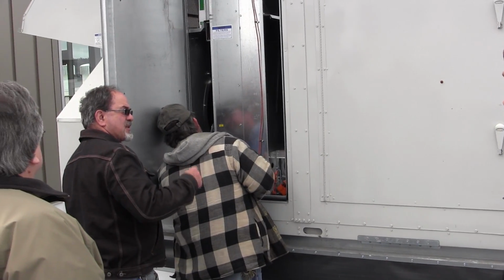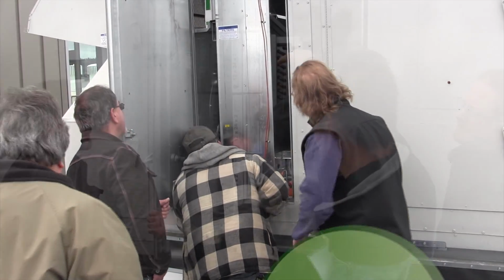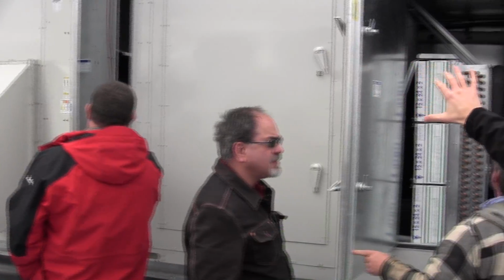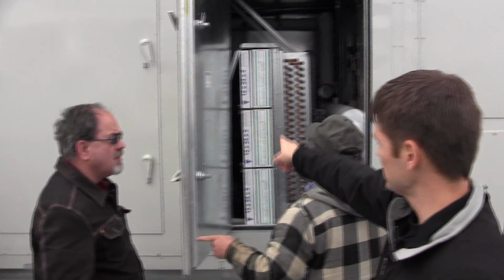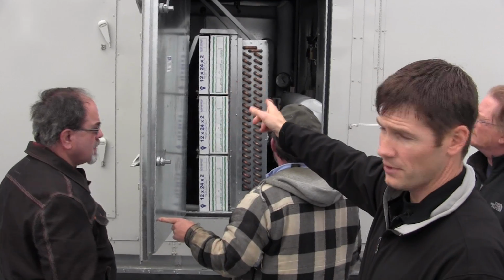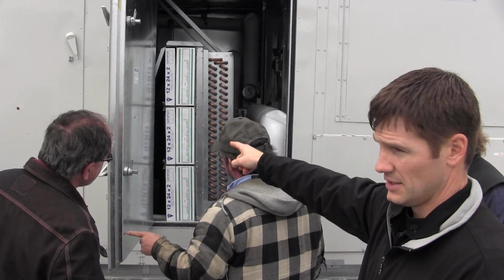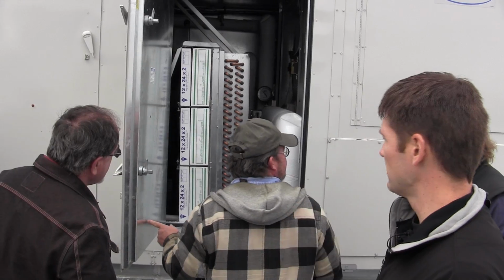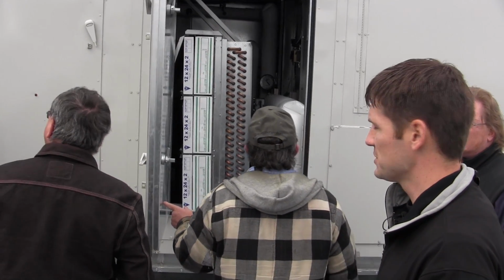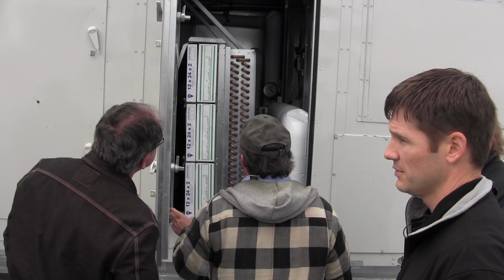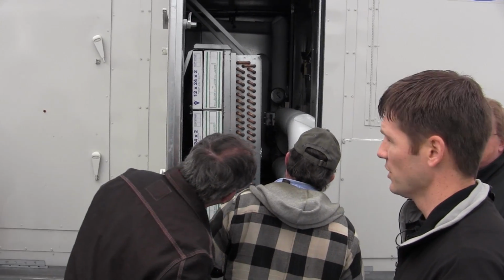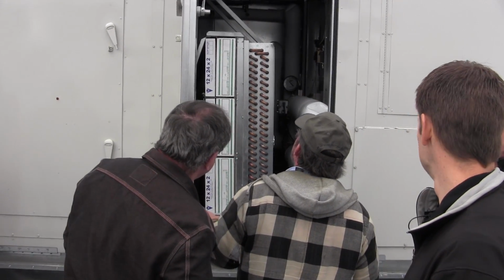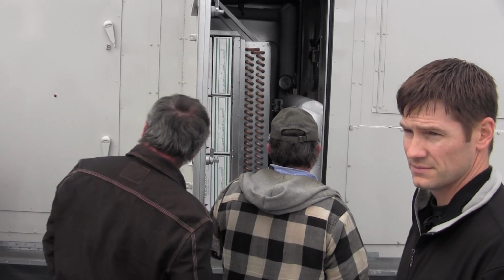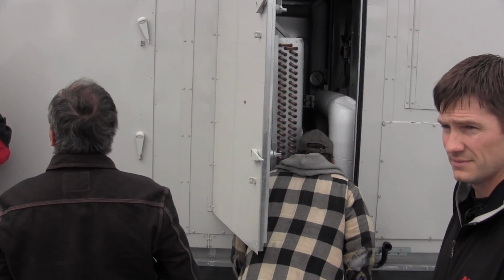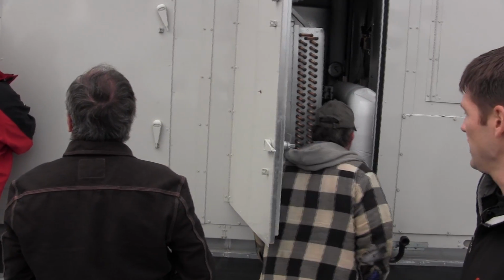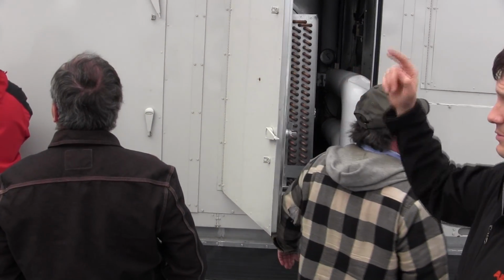That looks like a kind of velvet or something. That felt. It's something else. If it's going 100% outside air operation, that same air up there gets filtered here. And this is a 2-inch rack and a 4-inch rack. That 2-inch rack is redundant, so you can leave it in. A 2-inch rack, 30% filter is about 0.2 inches of pressure drop, so it's not a huge worry, but they are redundant. So the next time around when we change it out, we'll just leave it out. It's a little bit less maintenance. They might still be fairly clean. You could move them back there.